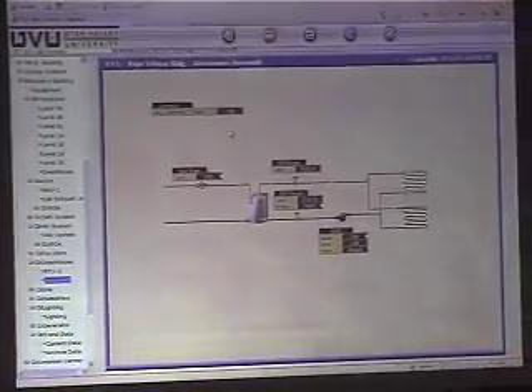So up on the roof, I'm not sure if you've seen that, but where you exit the greenhouse on the west side of it, there's a walkway that goes over to the west stairwell to go down. That walkway has a snow melt system underneath it. When we go up there, I'll show you where the outdoor sensor is, that's represented right here. It's actually mounted on the handrails as you walk down that path. So there's a small heat exchanger up there, as well as a control valve, and we modulate that to maintain 90-degree water out to that loop. So when there's a call for snow melt, this pump will turn on and this valve will open to maintain that temperature to that loop.